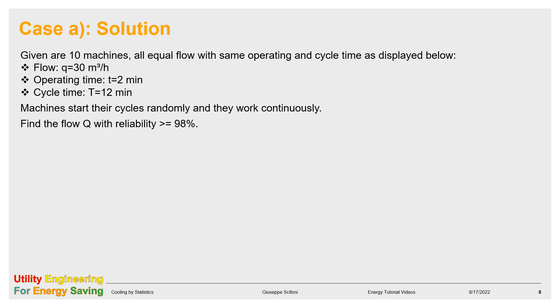Let's take a while now to define the reliability in a statistical way. Assigning the time frame of 24 hours or 1440 minutes, the design flow capital Q can stand the system operation up to 98% of that time. In other words, the system demand can exceed capital Q only for 2% of the operating time. When we choose the statistical approach, we assume the risk of undersizing the equipment, but this risk is reasonably small. The smaller is the risk we can accept, the more will be the capacity of the system. Eventually, we have to find a compromise.